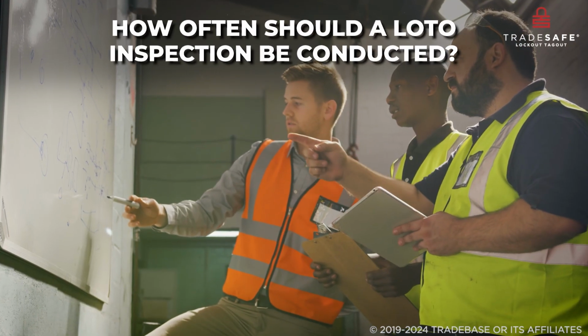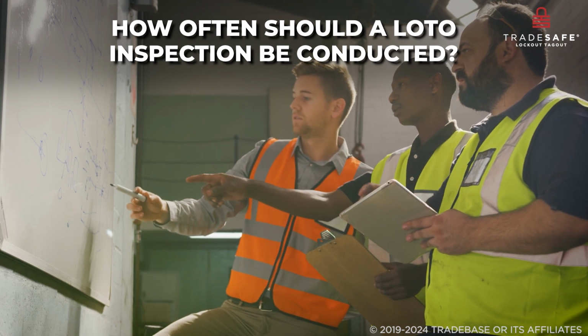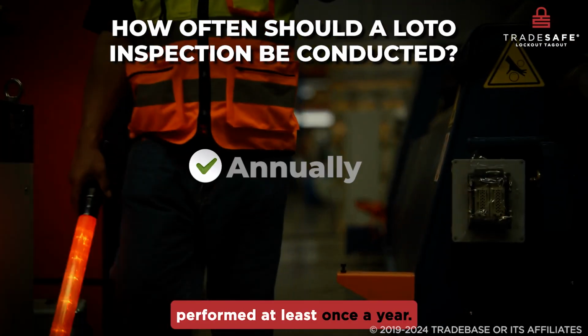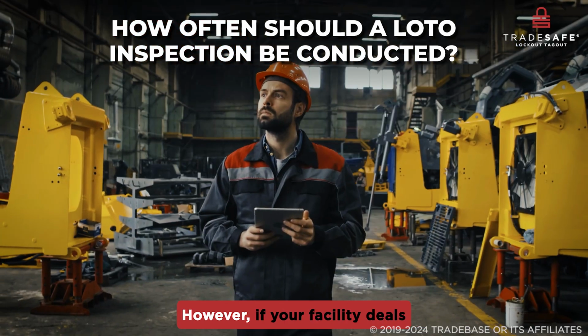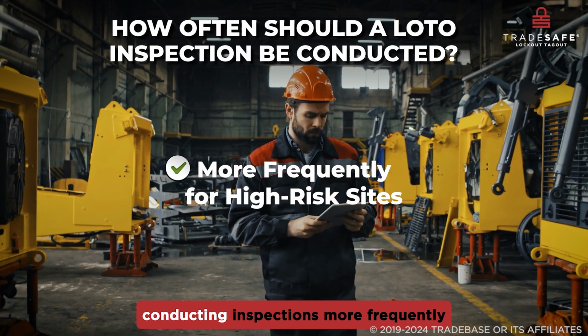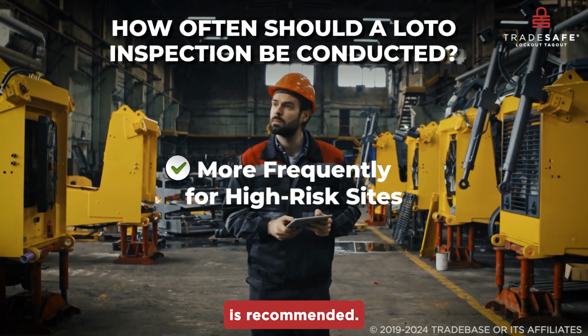So, how often should a lockout tagout inspection be conducted? According to OSHA standards, LOTO inspections must be performed at least once a year. However, if your facility deals with high-risk machinery or frequent maintenance, conducting inspections more frequently is recommended.